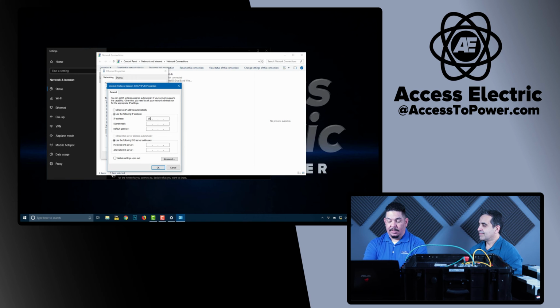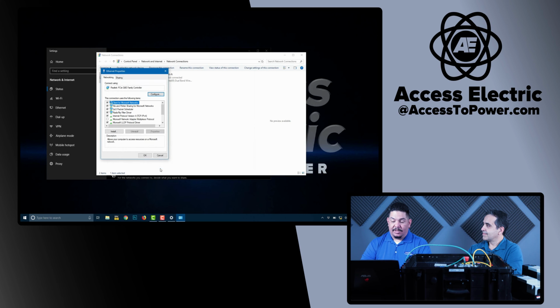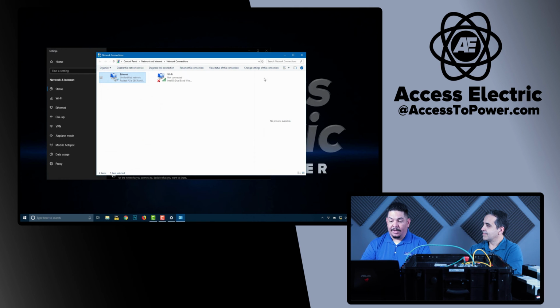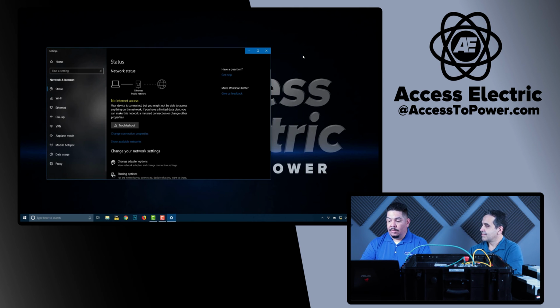Now, typically, what I do when I set my computer to join an industrial network is I use 254 for the last set of numbers because that's typically left open. It's the last number that's available in the IP range. I know that this network is 192.168.1, so my computer's 254, and I should be able to see these devices. Subnet's 255, we can leave the gateway blank for this. Hit okay here, and we should be set.